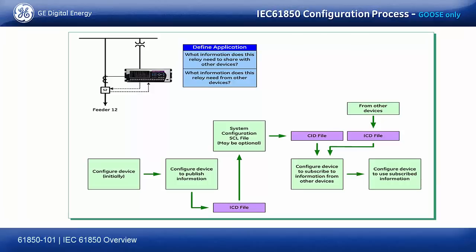I don't have an SCD file as the master for everything. I just configure the individual devices. Now, 61850 purists, and I brought this up delivering a conference paper, will blanch at this. They think this is heresy that you don't have an SCD file for the whole substation. My response is, why do that master stuff when I'm going to configure a handful of devices simply to do GOOSE messaging? It doesn't make sense, and with just GOOSE messaging, I can do it faster by configuring the devices normally than I can doing the master thing.